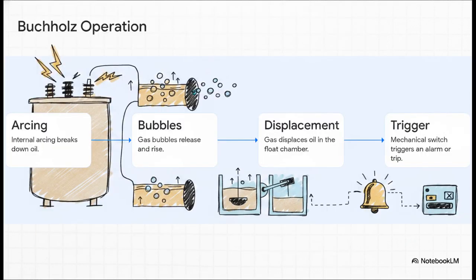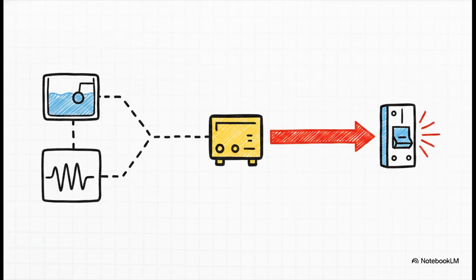Then, over on the mechanical side, we have the Buchholz relay. This is such a cool physical piece of safety gear. It's basically a literal bubble detector sitting right in the pipe between the main tank and the oil expansion conservator. When internal arcing breaks down the oil like we talked about earlier, it releases combustible gas bubbles. Those bubbles naturally rise up and displace the oil inside the Buchholz float chamber. As that oil level drops, a mechanical float switch drops with it, which physically triggers an alarm or a trip command.